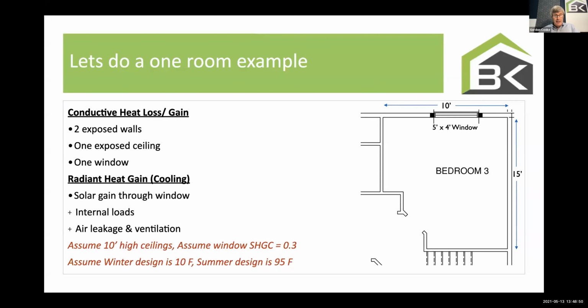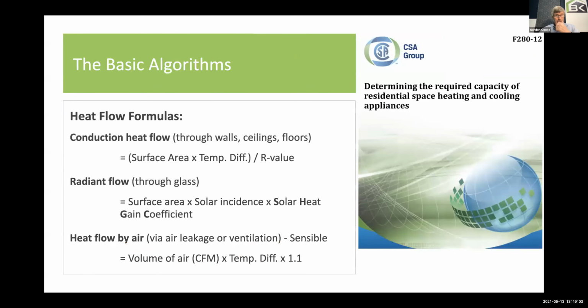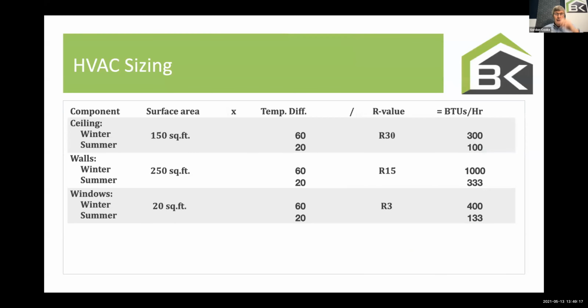In this case, I'm going to say to you, let's assume 10-foot high ceilings. Let's assume a window solar heat gain of 0.3. And let's assume a winter design of 10 degrees Fahrenheit and a summer design of 95. Just so you see some relatively easy math. And remember, we're going to apply these 3 basic formulas: the conduction flows through the walls and the ceiling, the radiant flow through the glass, and we're going to think a little bit about air leakage, and then I'm going to tell you how they actually do it, and we'll see what happens. So here's the spreadsheet, right?